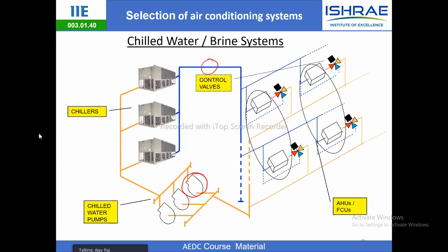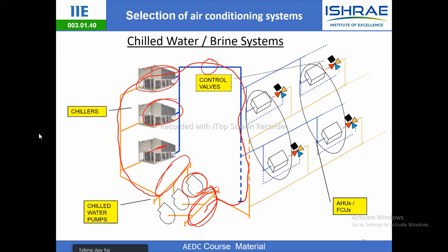then these chillers can be in negative pressure, because they will also suck. When they suck, you have minimum pressure here and maximum pressure over there. So your pressure keeps decreasing as the water travels from this place and comes back. That's why we always try to keep our chillers in positive pressure.